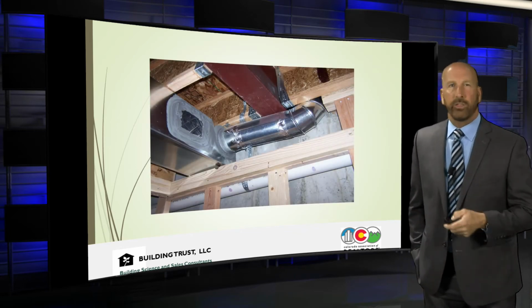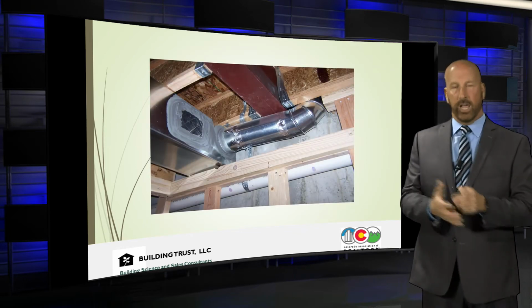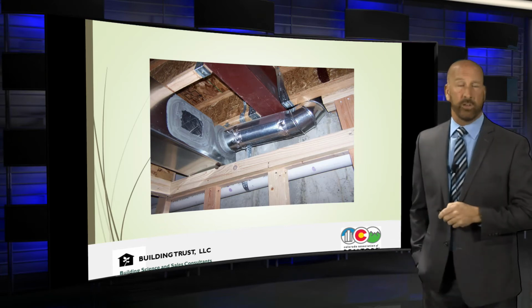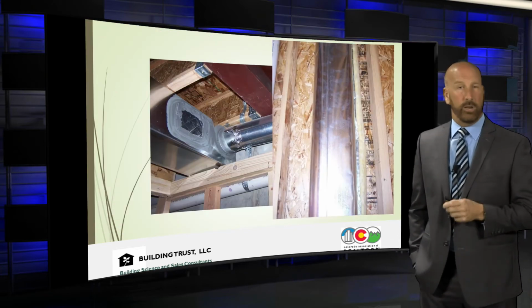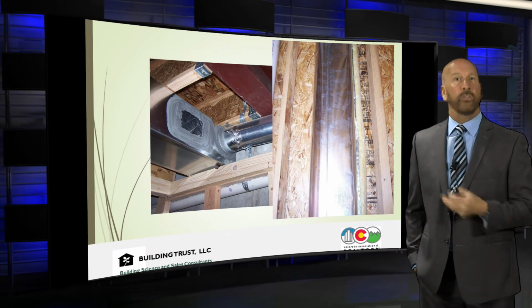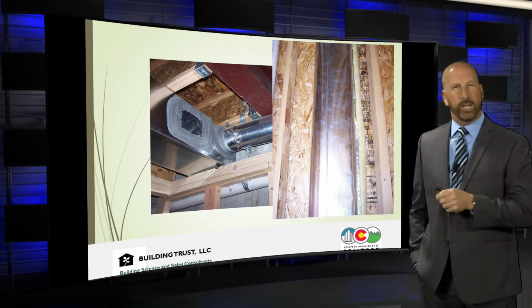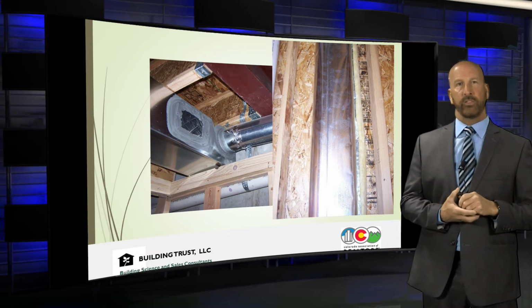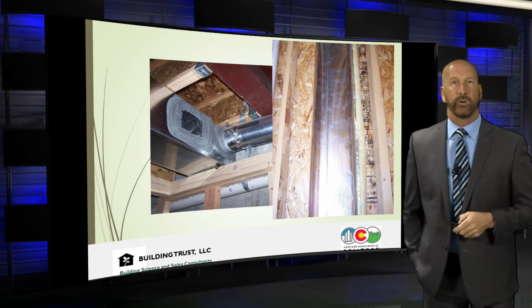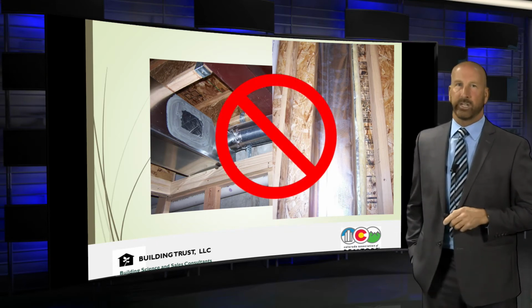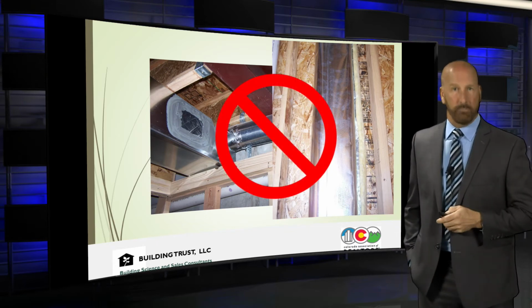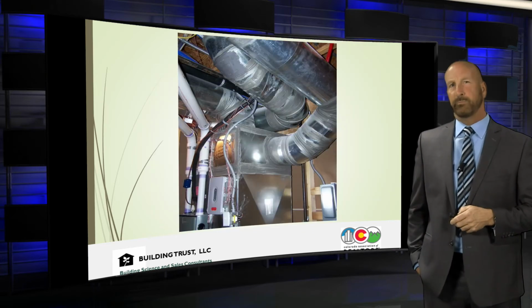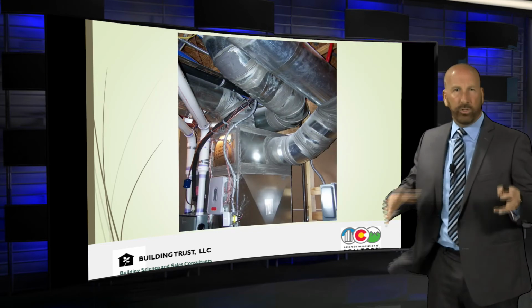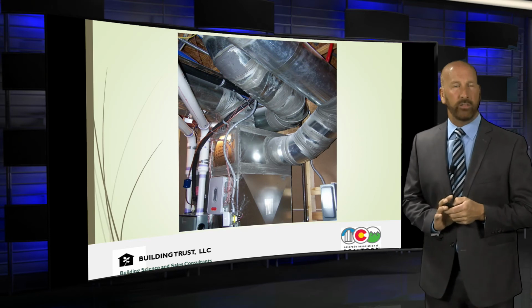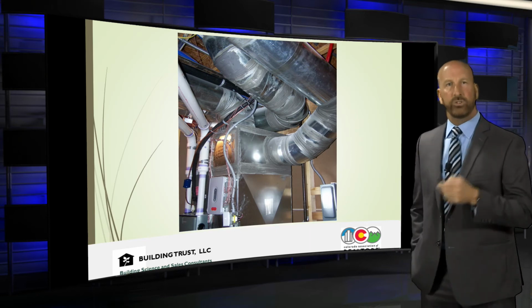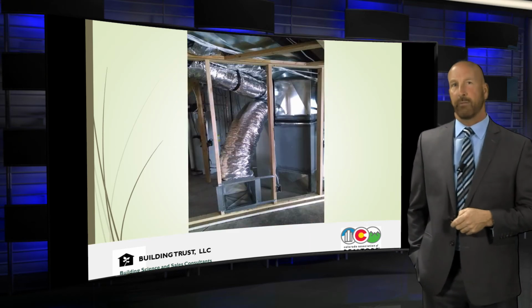We've also learned about other things like stop putting vents and registers and heat runs up against foundation walls. We've stopped putting heat runs in wall assemblies on the exterior of the home. It doesn't make sense to stick a duct in an exterior wall when you can't put insulation behind the duct. We've learned that that's no longer acceptable, and most times it's not even allowed by code. So we've done a much better job when it comes to ducting. We put the stuff inside the house and we seal it with mastic because airflow is huge when it comes to comfort, temperatures, and performance.